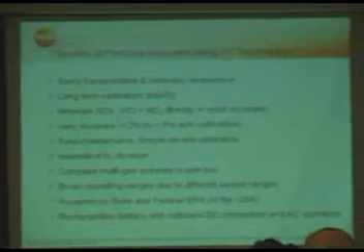This is a very low reading, and we have to make sure that even such low readings can be measured with our instrument, not using reference technology and heated lines, because for the service technicians this is not really comfortable to use such sensible equipment in the field.